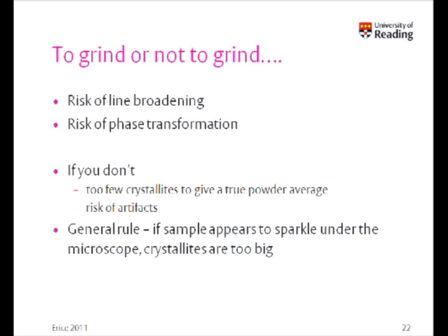General rule, if the sample appears to sparkle under the microscope, the crystallites are too big. If they're sparkling a lot, then you should be getting in and trying to pick a crystal out and speak to your friends with single crystal diffractometers. But even those that are too small for conventional single crystal can still be too big for powder diffraction.